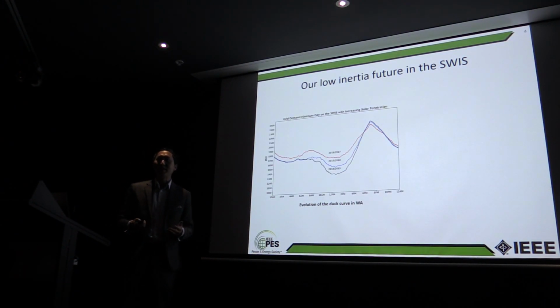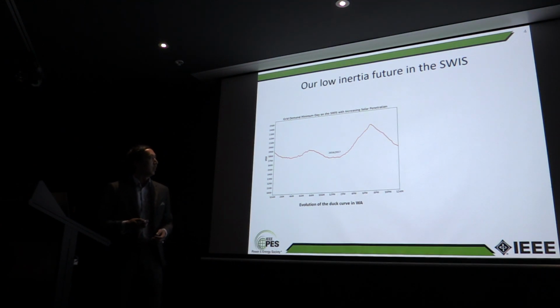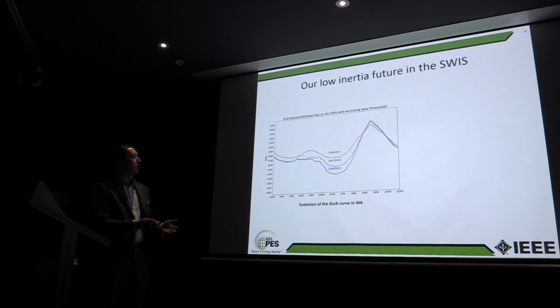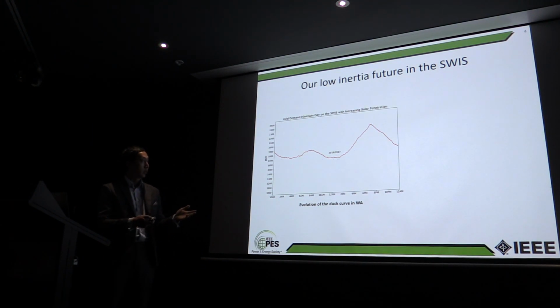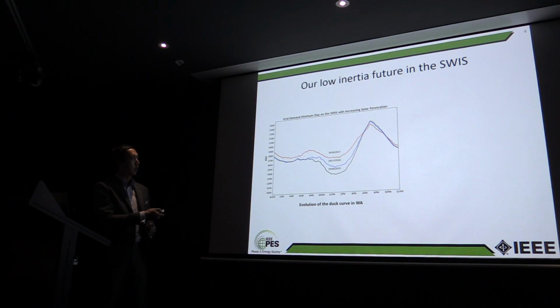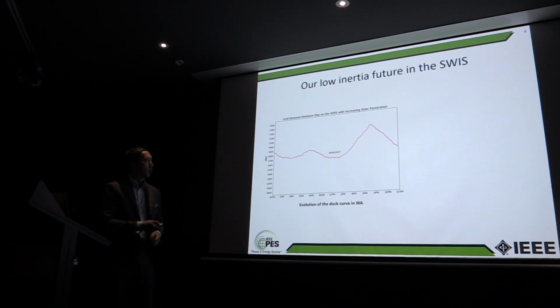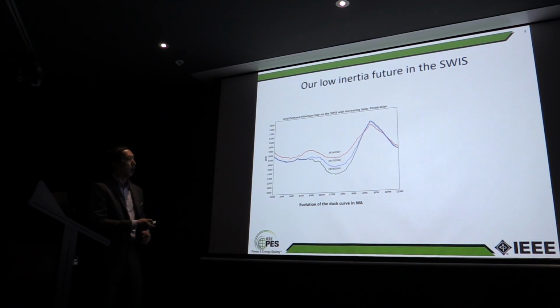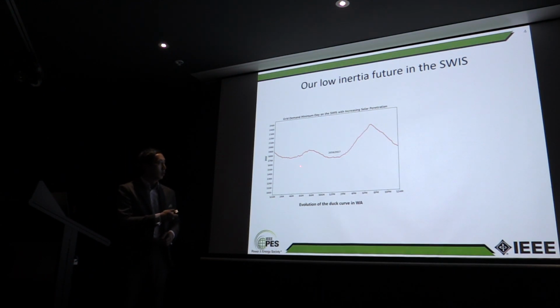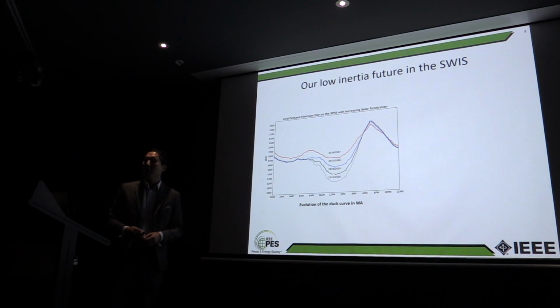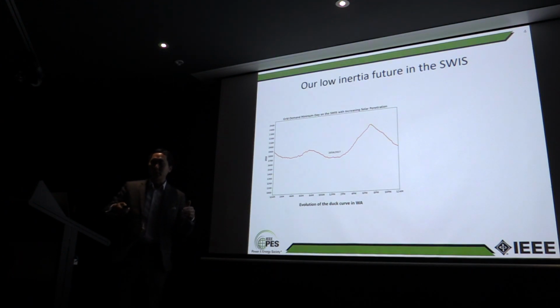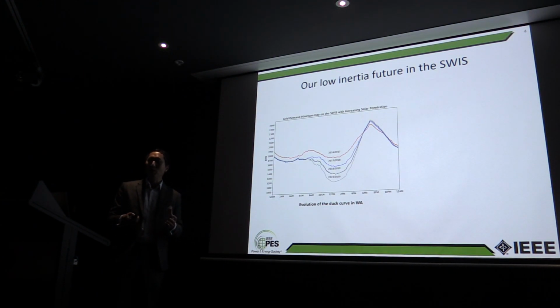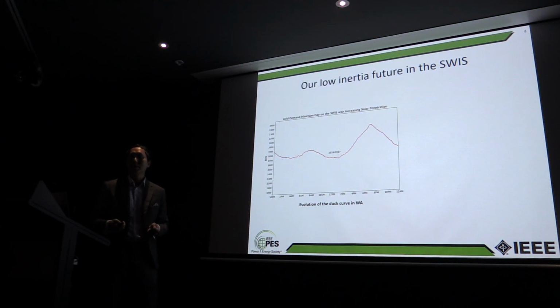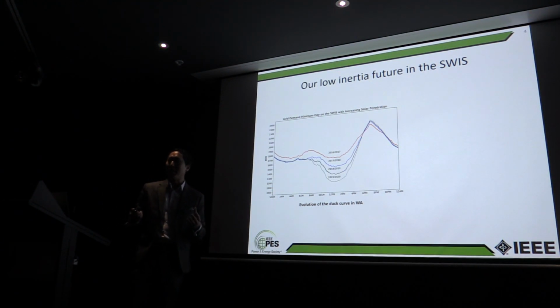So I can't have a presentation about inertia without a duck curve. And so here's a duck curve as it's evolving over time and into the future. The first couple of years are historical, and then the next couple of years are projected forwards. And what you can see here is this hollowing out in the middle, where rooftop solar is coming in and the loads are becoming very low. And the problem with this is that when the loads get lower, the rooftop solar is actually displacing synchronous machines, or the machines that have rotating inertia.